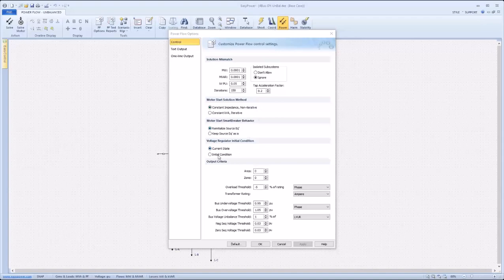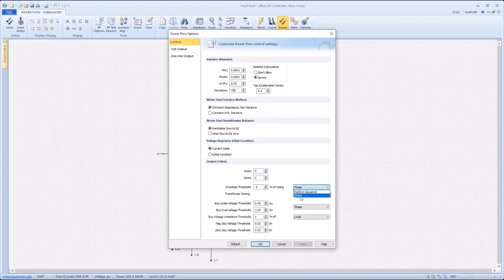Taking a closer look at the output criteria, one can see that overload thresholds as well as voltage thresholds can be specified. In addition, these thresholds can be specified further based on the desired type of comparison. For example, the overload threshold can be set to either positive sequence or phase.